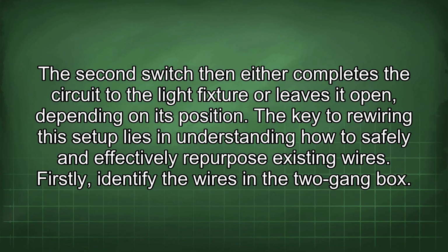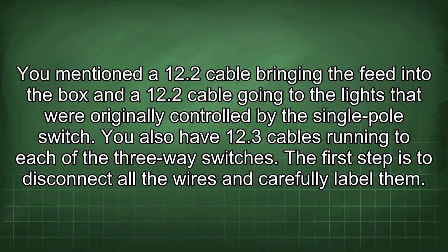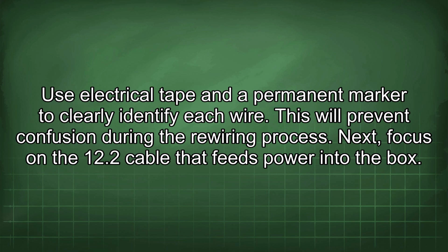Firstly, identify the wires in the two-gang box. You mentioned a 12.2 cable bringing the feed into the box and a 12.2 cable going to the lights that were originally controlled by the single-pole switch. You also have 12.3 cables running to each of the three-way switches. The first step is to disconnect all the wires and carefully label them. Use electrical tape and a permanent marker to clearly identify each wire. This will prevent confusion during the rewiring process.